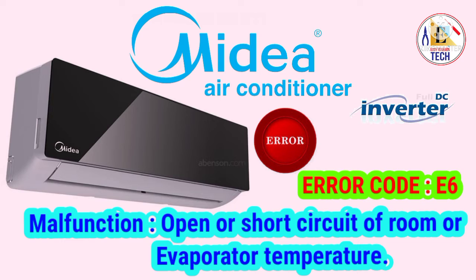If the placement is good, then you have to check the resistance of your room or evaporator temperature sensor. If the resistance is not good, you have to change the sensor and you will get the solution. If the resistance is good, then you have to check the connector of your sensor. If the connector is not connected properly in the PCB, at that time also we can get this error. And if the wire between the sensor and the PCB is cut or damaged, at that time also we get this error E6. Then you have to check the connection and correct it properly.